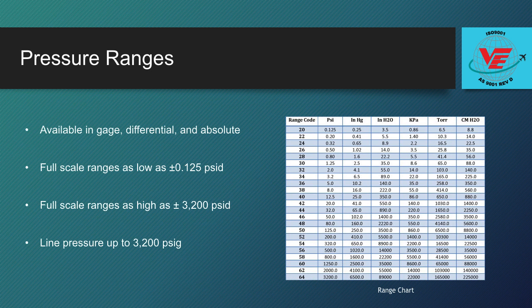The P55 is available in a wide variety of pressure ranges and can be configured for absolute, differential, or gauge measurements. The P55 can be ordered with a full scale as low as 0 to plus or minus 0.125 psi, with a standard accuracy of 0.25% full scale and optional accuracy of 0.1% full scale or better. The P55 is ideal for precise measurements over very low pressures.